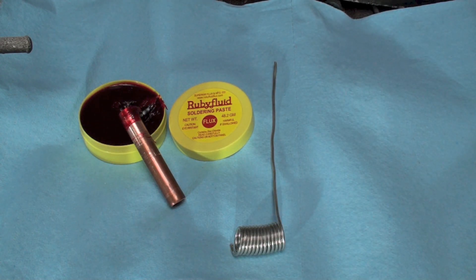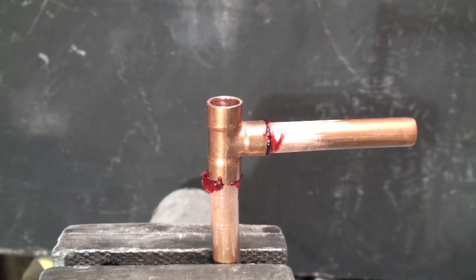We're going to go ahead and solder three joints with just a propane torch. Propane torch is pretty good for this because the heat isn't real high, and you don't want real high heat - you don't really want this pipe too hot. It's a fairly large volume flame. Here's my fitting.